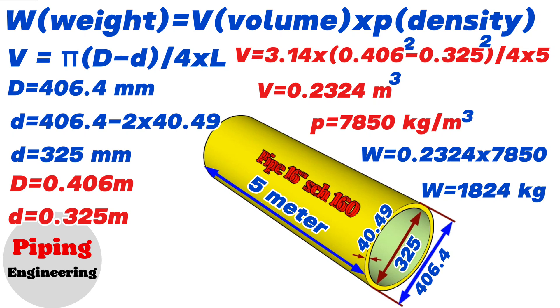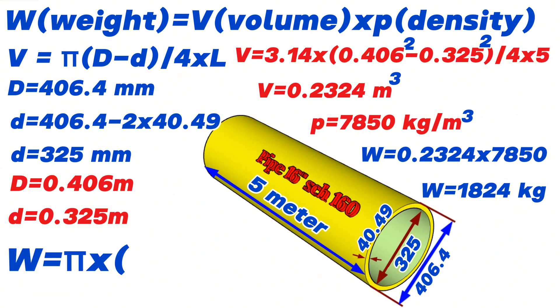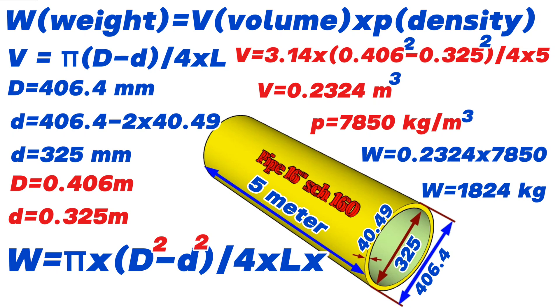Summarizing what we learned in this video, we can use this combined formula to find the weight of a pipe: Weight equals π multiplied by (outside diameter squared minus inside diameter squared) divided by 4, multiplied by the length of the pipe, multiplied by the density of the pipe material. By using this method, you can easily calculate the weight of pipe pieces from any pipe drawing.